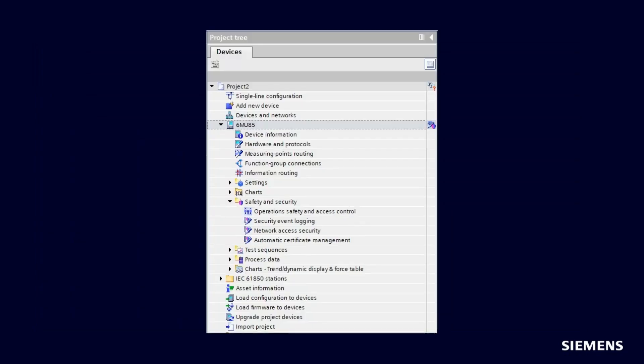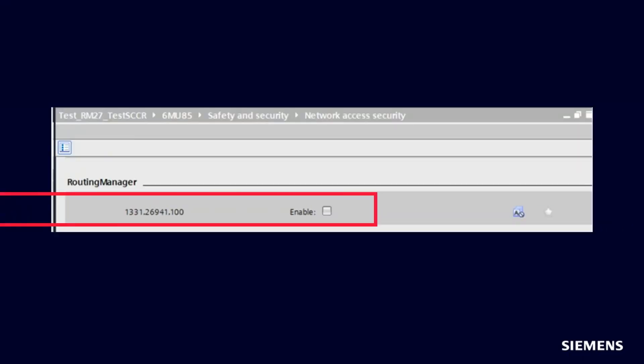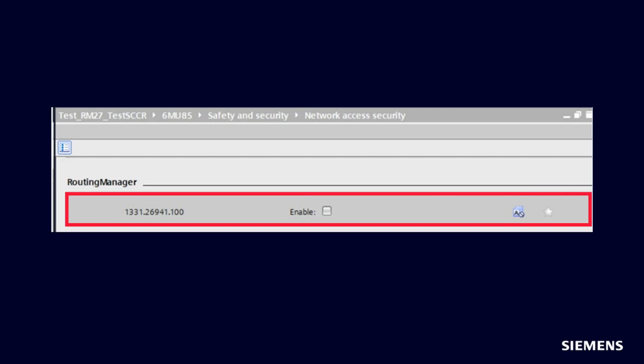The configuration of the routing manager is located in DIGSI 5. Click Safety and Security, then choose the Network Access Security option. The routing manager is disabled per default. In order to use the routing manager functionality, please click Enable.